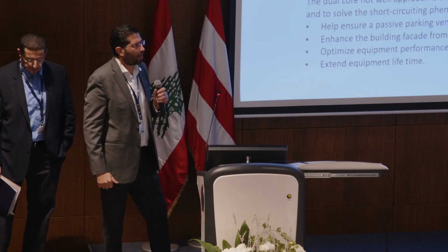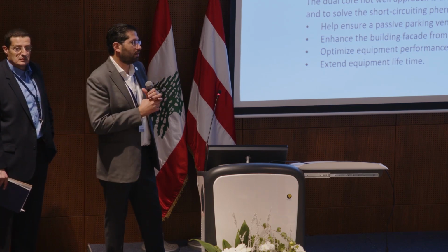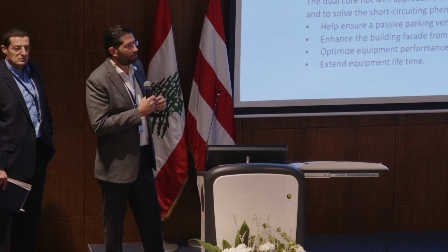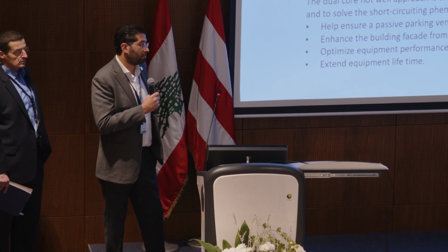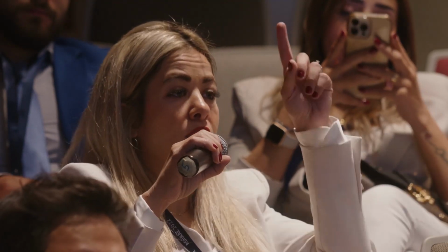Back to your first question, it depends on the height of the building. We've read multiple studies on this problem. As you go up, the heat will accumulate and there will be a temperature gradient. But we've done multiple projects, enhancements on such cases in Dar al-Handasa to prevent this. And I agree with you, but again, it was like G+26, Kfouri building, and we did CFD back then, and we didn't need any additional shaft for the outlet or exhaust of the condensing units.